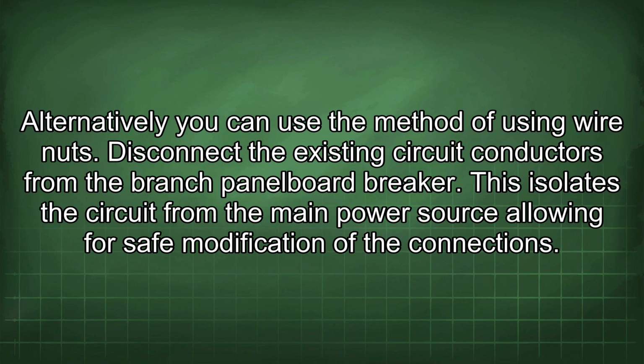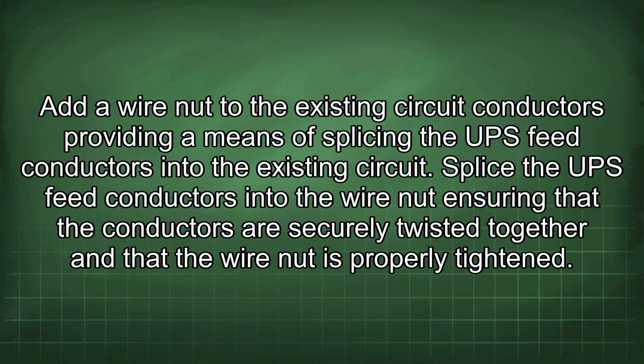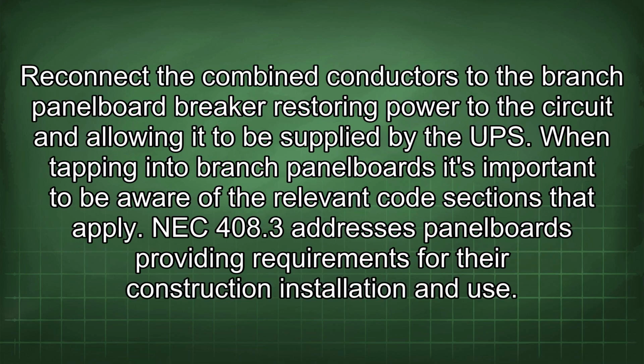Alternatively, you can use the method of using wire nuts. Disconnect the existing circuit conductors from the branch panel board breaker. This isolates the circuit from the main power source, allowing for safe modification of the connections. Add a wire nut to the existing circuit conductors, providing a means of splicing the UPS feed conductors into the existing circuit. Splice the UPS feed conductors into the wire nut, ensuring that the conductors are securely twisted together and that the wire nut is properly tightened. Reconnect the combined conductors to the branch panel board breaker, restoring power to the circuit and allowing it to be supplied by the UPS.